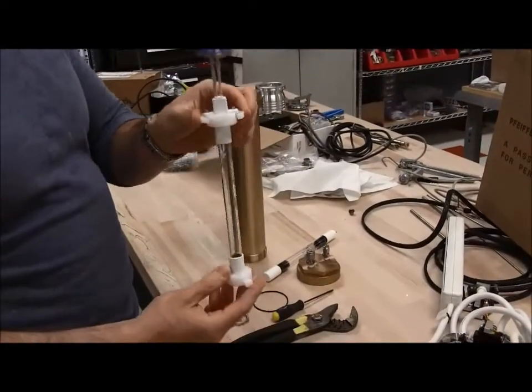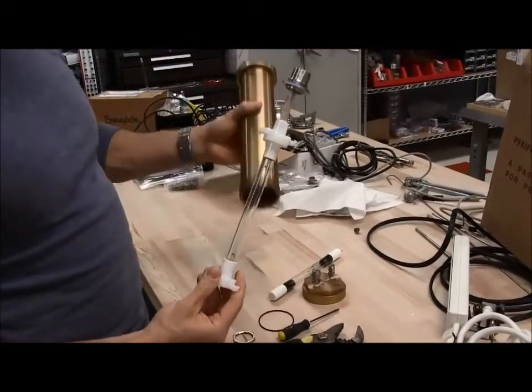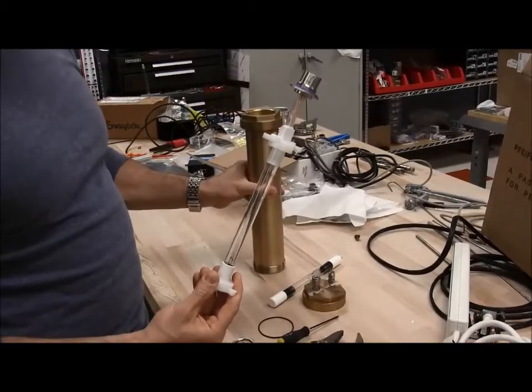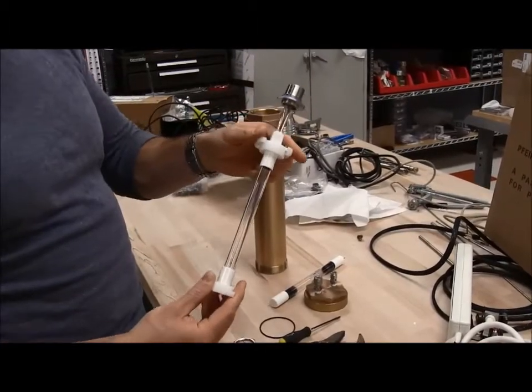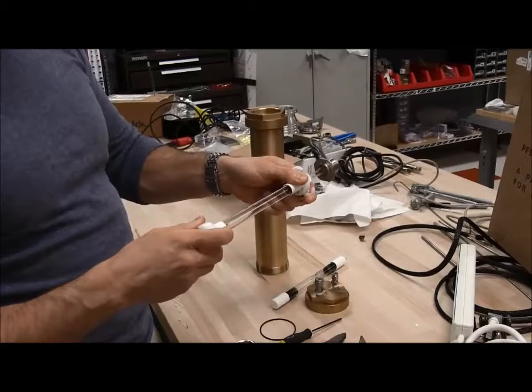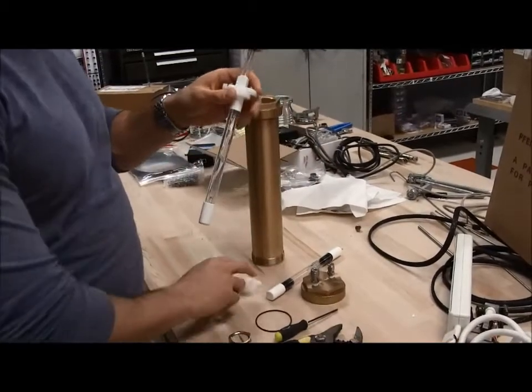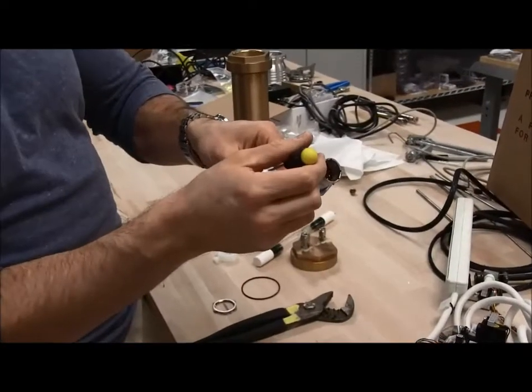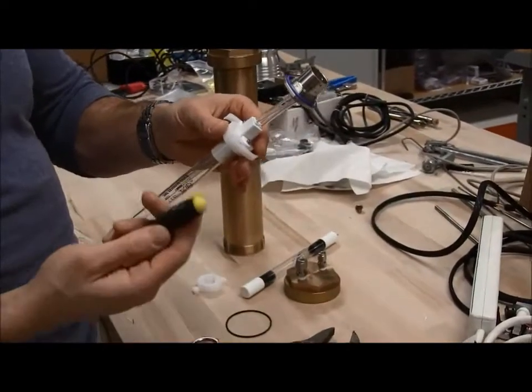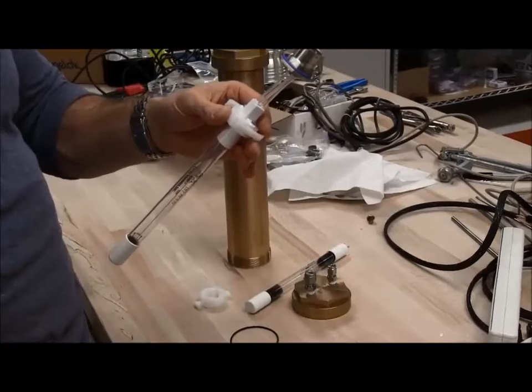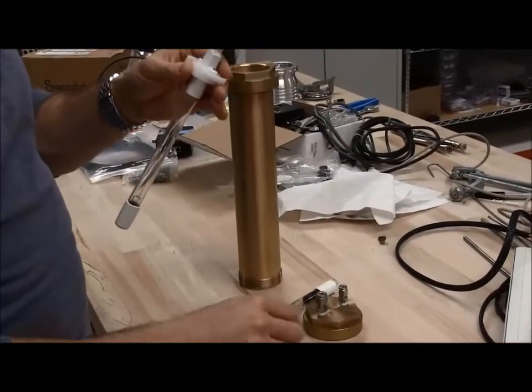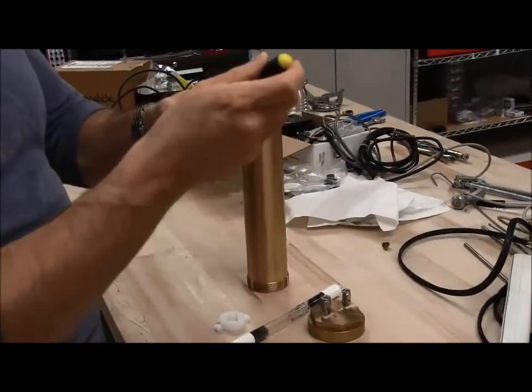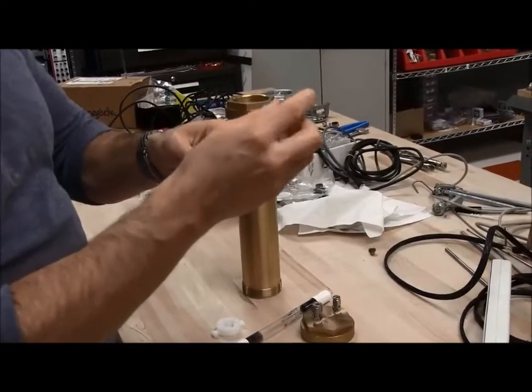These standoff pieces center the lamp on the inside of the ozone chamber, so those just need to be mounted on both sides when you're taking it out and putting it back on. If I were to replace the lamp, just take my bottom cap off. Just unscrew these screws with a 3/32 hex driver, and there's not much more to it other than that.